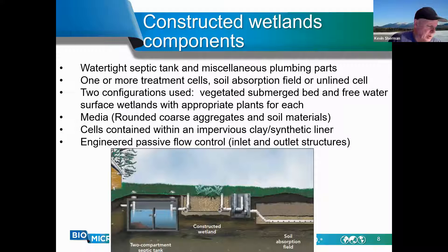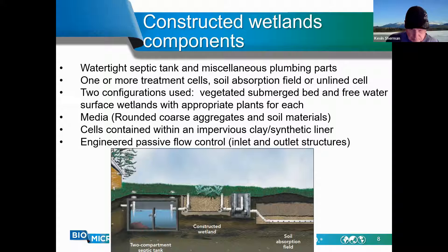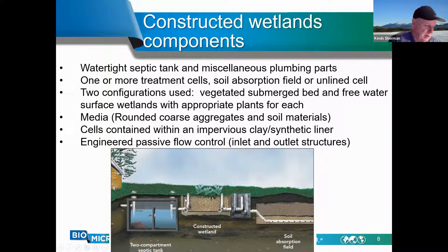The components of a constructed wetland are a watertight and structurally sound septic tank, a treatment cell or multiple cells, and plants. A single treatment cell is the minimum acceptable. Treatment cells can be either lined or unlined, with a free water surface or with vegetation, as shown in this artistic rendering, where the plants are rooted into gravel and the water level is set by the elevation of the outlet device. That elevation sets the water level to just underneath the ground surface.